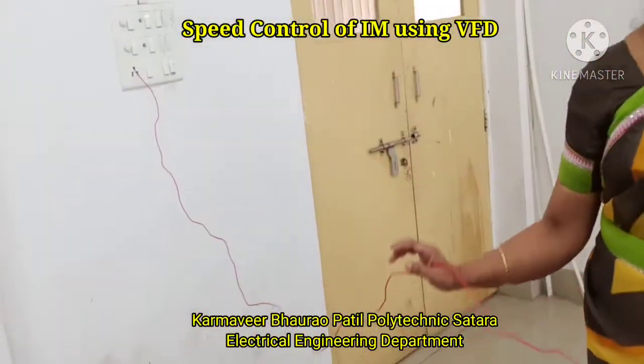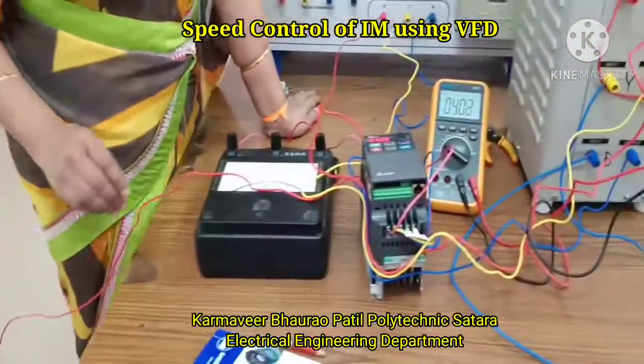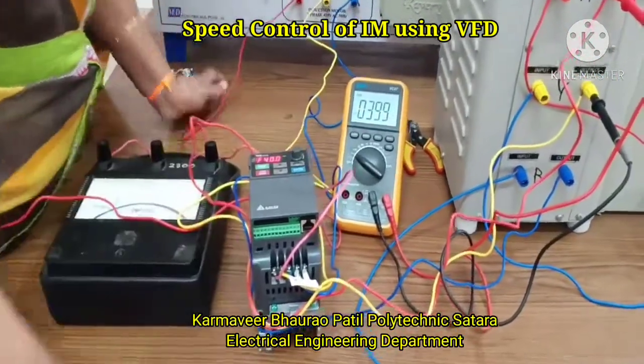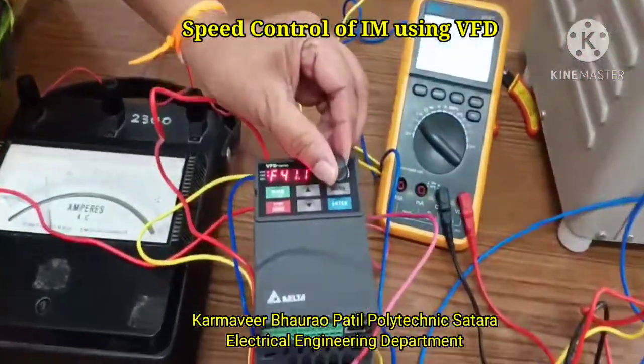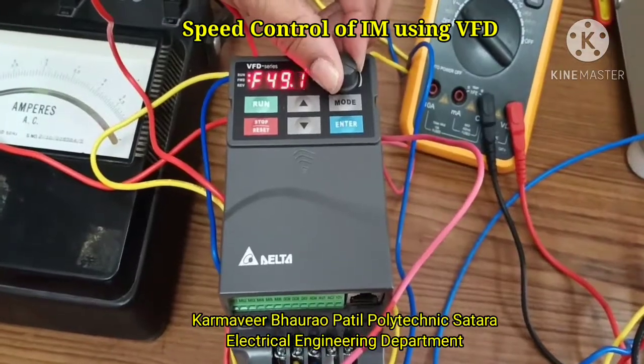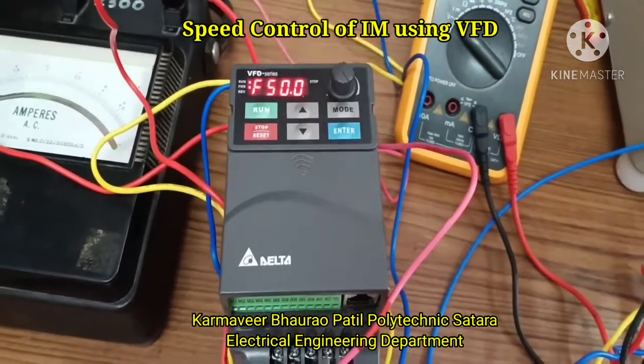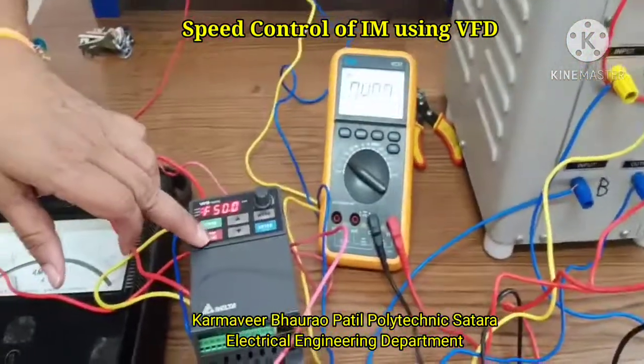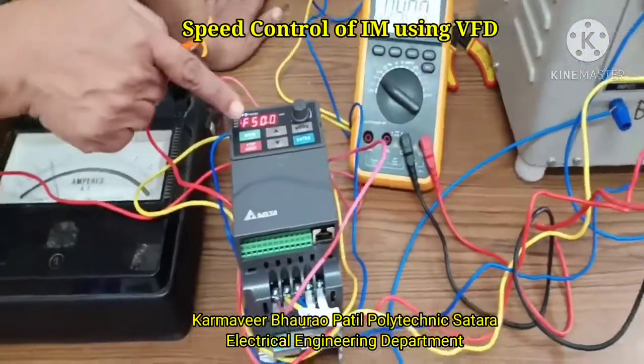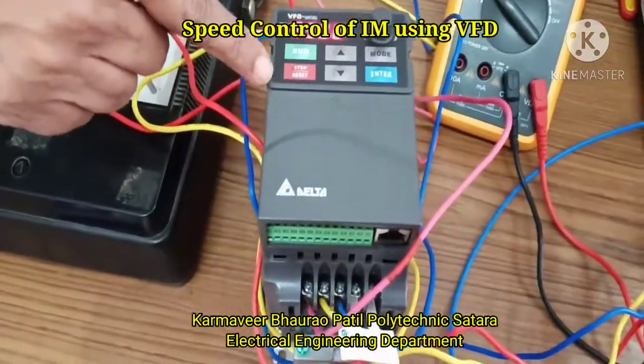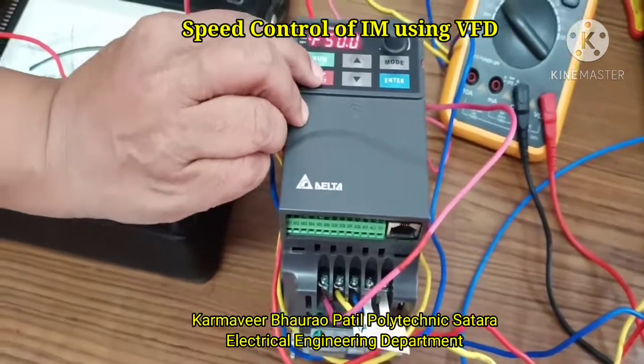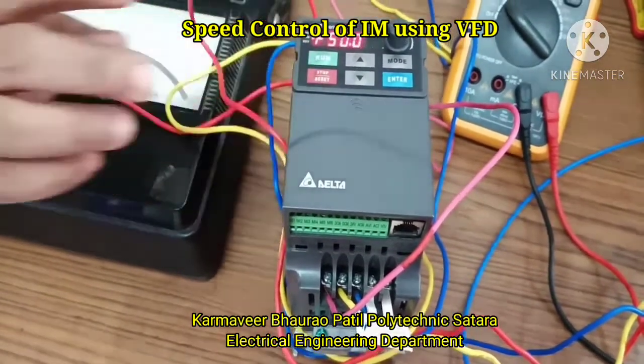So now we are going to stop the motor. Before that I will readjust the frequency to 50 Hertz, because that is our normal operation. 50 Hertz, 400 volt input, and now we stop the motor. To start the motor we pressed the run button. Now to stop the motor we will press the stop button. The motor will stop.